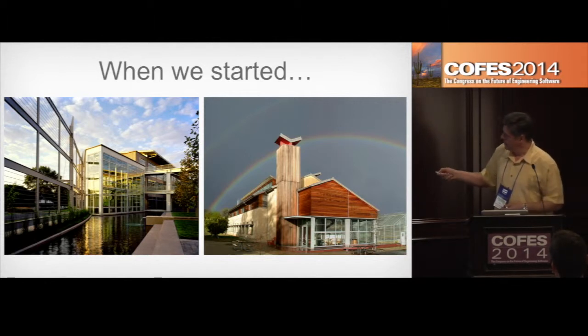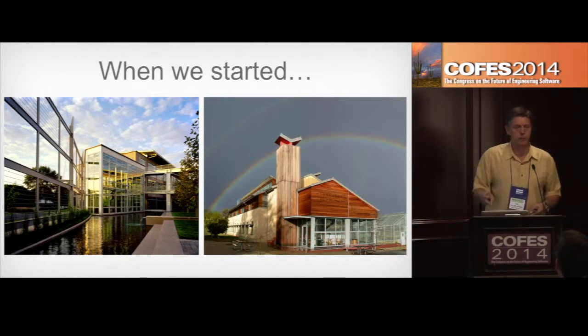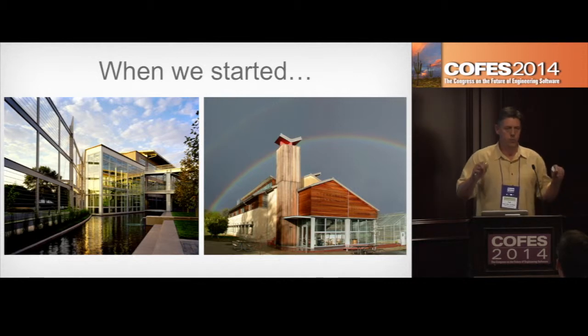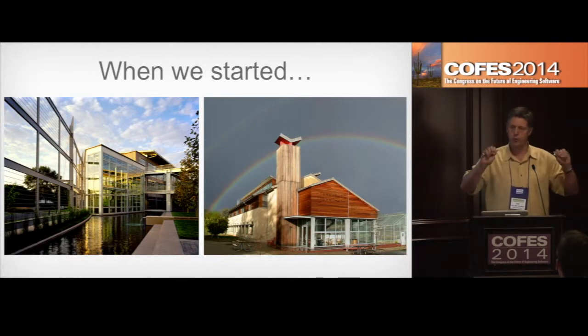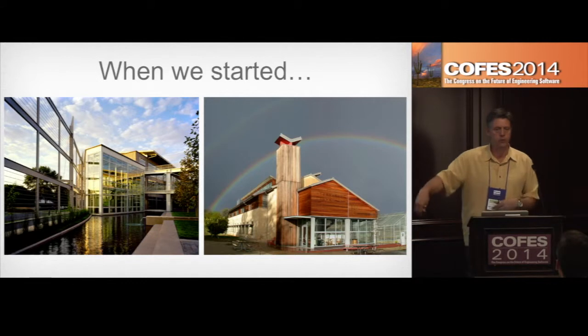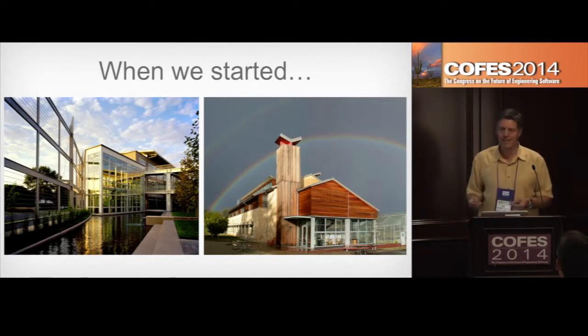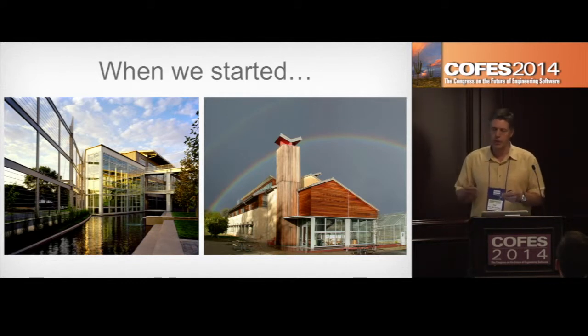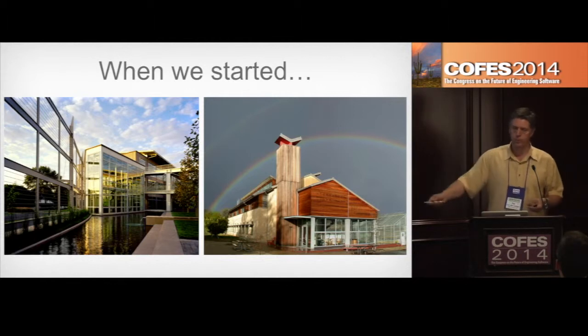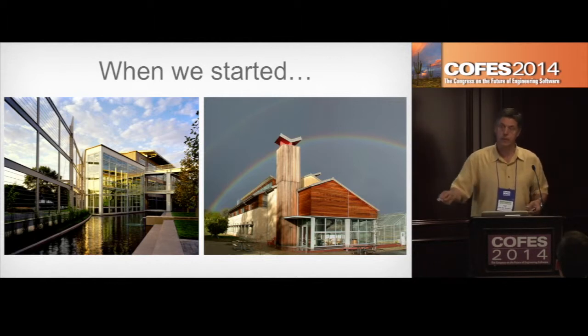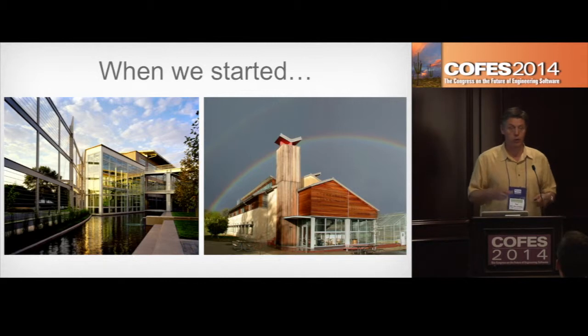At night, there's a sprinkler system attached to the standing seam roof of this building. When dew point got to 55, we'd spray water on the roof, which would take that cool water into a thermal storage tank. During the day, as the building's mass came up in temperature, we'd pipe the cool water through the radiant piping system in the slab - another low-tech solution for a lab building that uses 70% less energy than a normal lab.